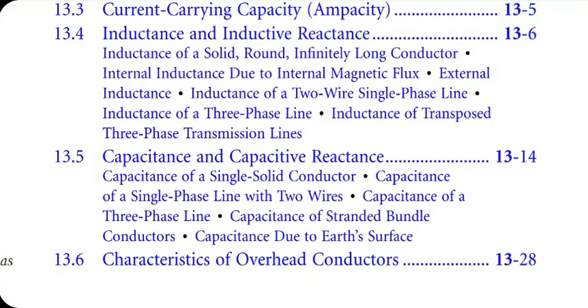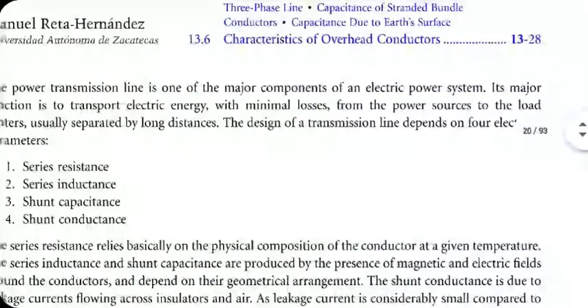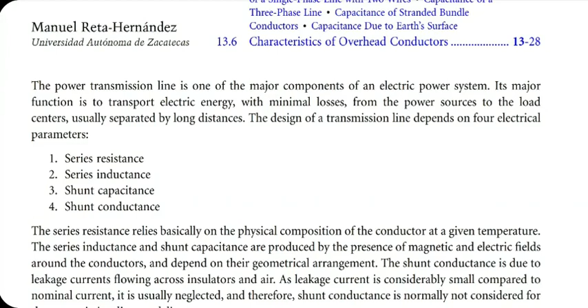Capacitance also has a lot of parameters that affect it. Earth has its own effect on capacitance. I was ignoring that in the calculations that I did just now. For three-phase systems, again, if it is not balanced, you may have to have three different capacitance values. Again, if the lines are bundled together, like several conductors bundled together in a single conductor rather, or strand rate, etc., all that affects capacitance value. Of course, this definition is well known to you, so I don't have to stress on that again. But read it a little bit carefully. RLGC, they are dependent on a lot of practical things that cannot be built into the simple formulas that we were using in the solved numerical problem.